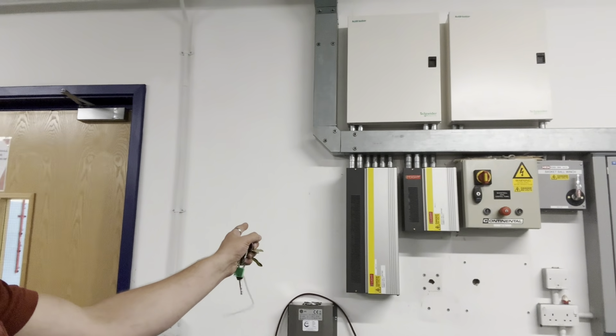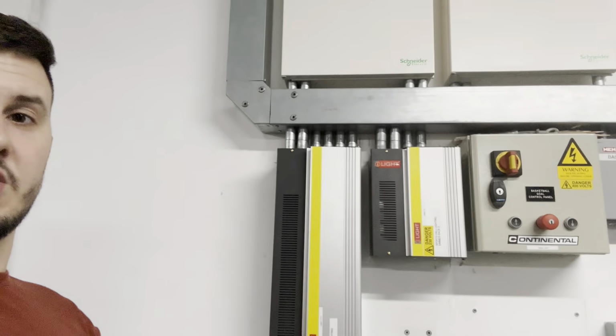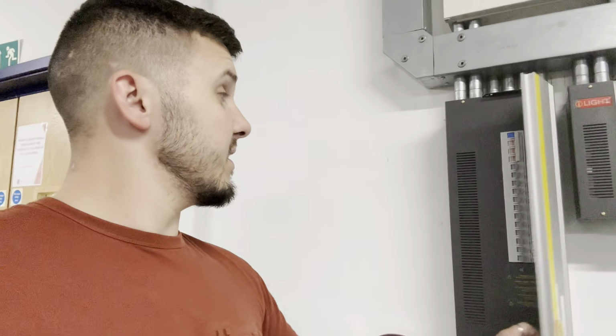56 light fittings changed over - what a horrible job. 24 volt switching, old dimming racks repurposed essentially as distribution boards for circuit breakers, and 2 panels, one with all the contactors, one with the transformers and primary contactors. Didn't get to show you too much, which I'm really sorry about, but I've been really up against it, I'm not going to lie. It's taken me longer than I was hoping, but it's been an absolute mammoth job.